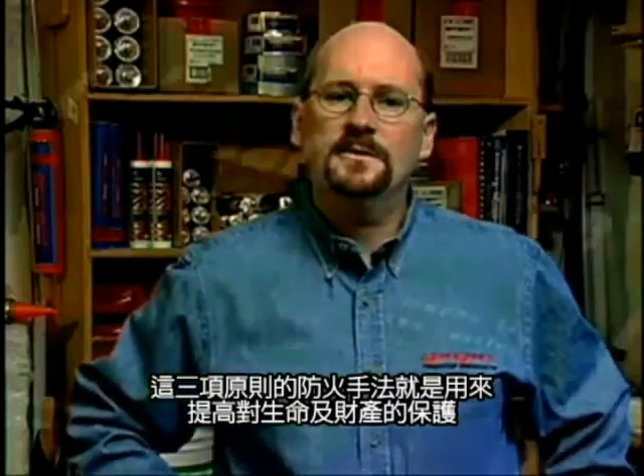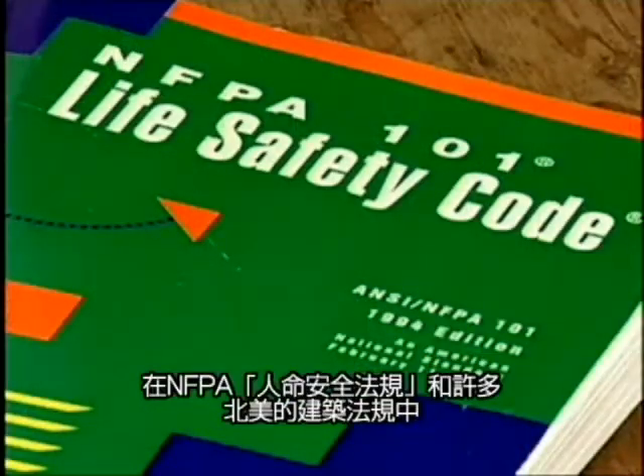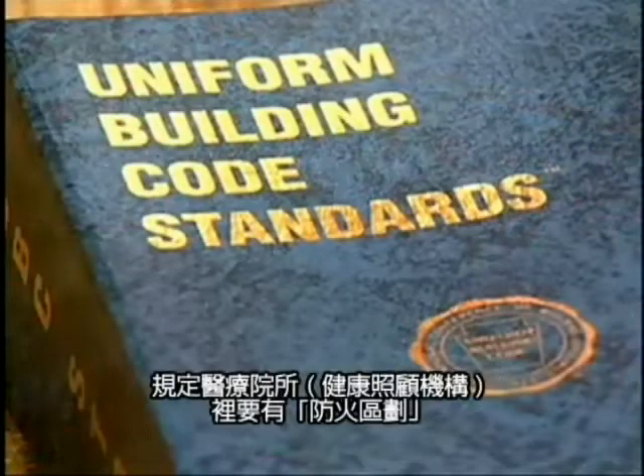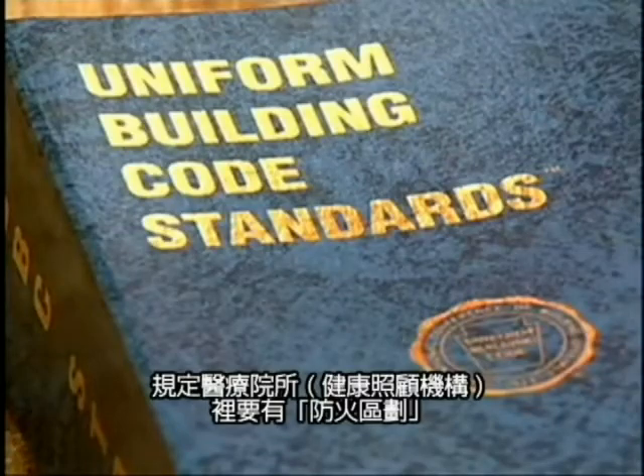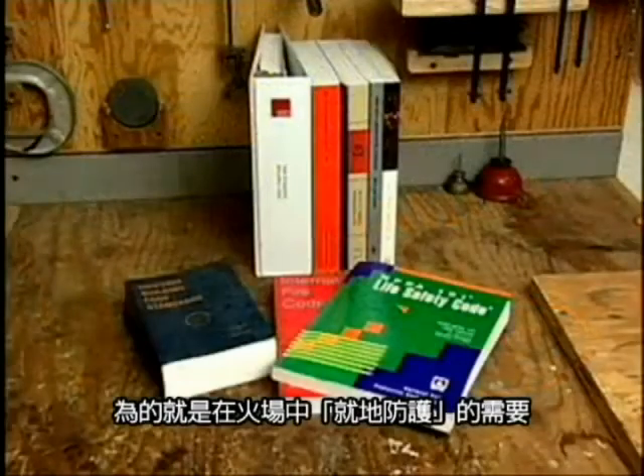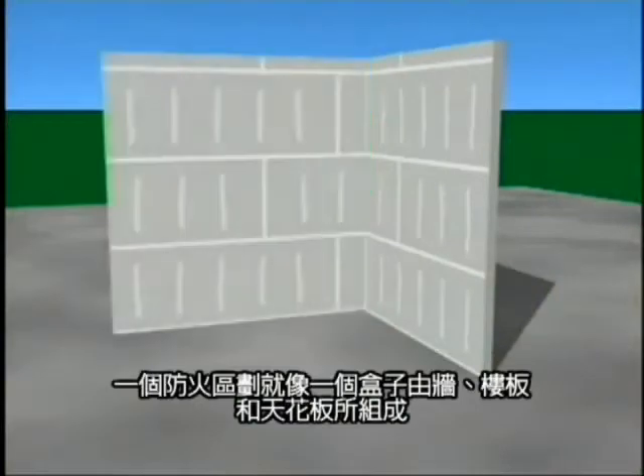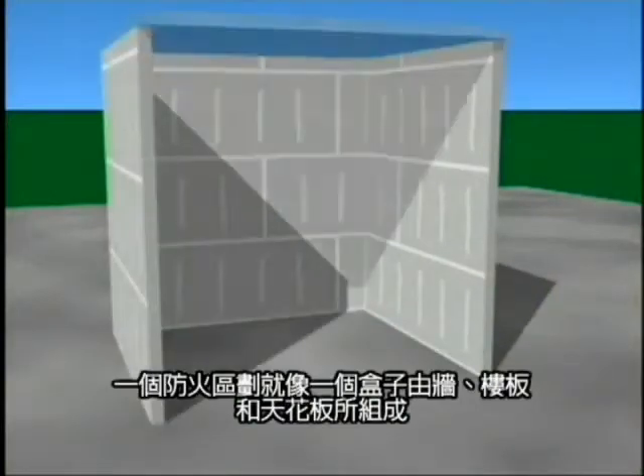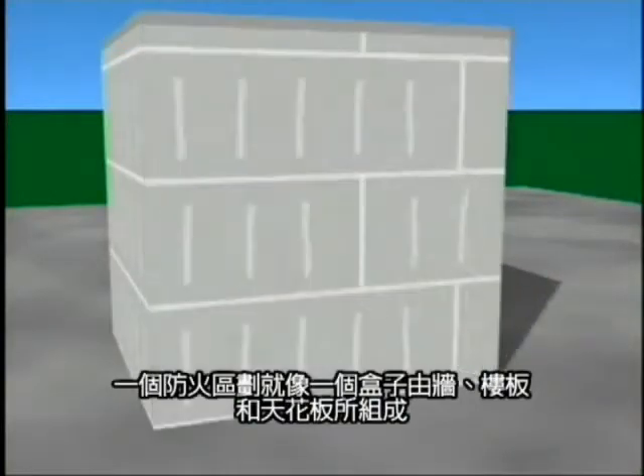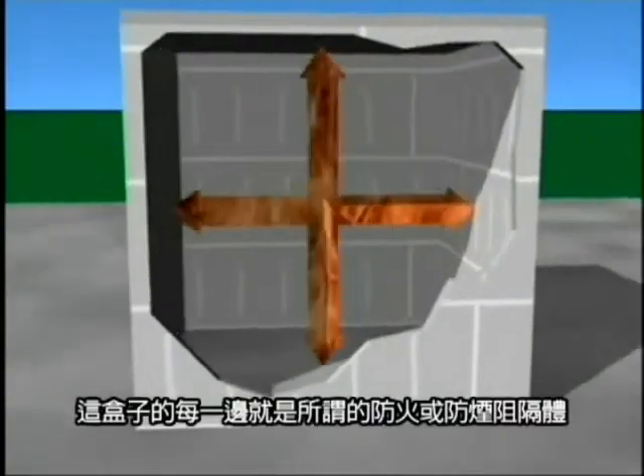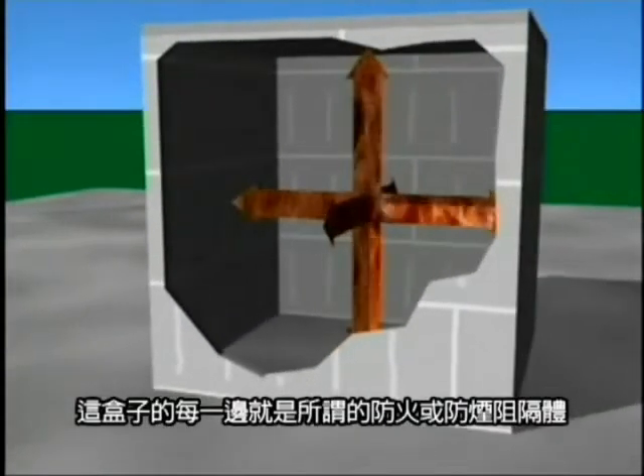This three-tier redundant approach to fire protection is designed to improve the odds for life safety and the protection of property. The NFPA Life Safety Code and all model building codes in North America mandate compartmentation in healthcare facilities due to the need for defending in place in a fire. A compartment is like a box made up of a floor, walls, and a ceiling. Each side of the box is known as a fire or smoke barrier.